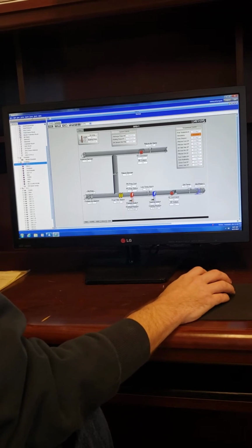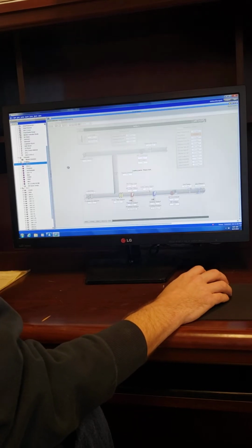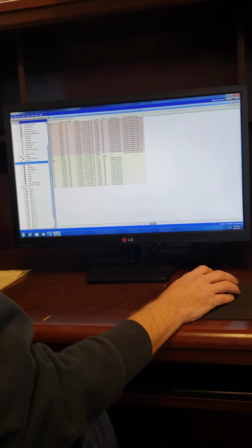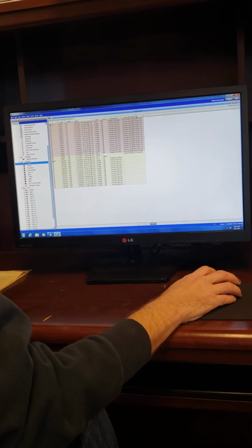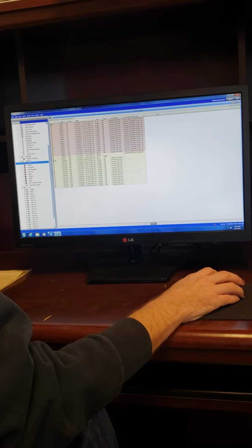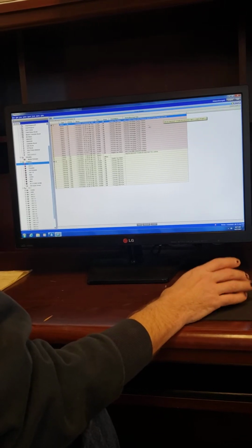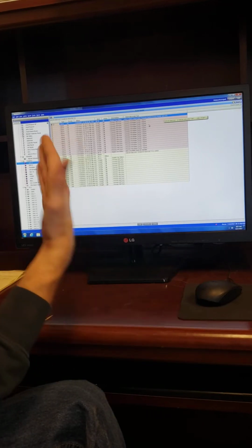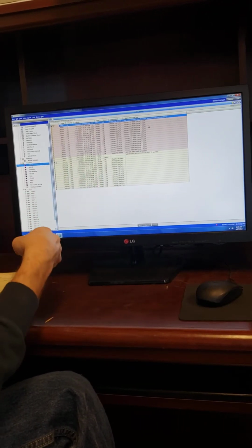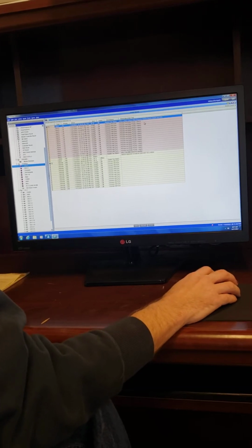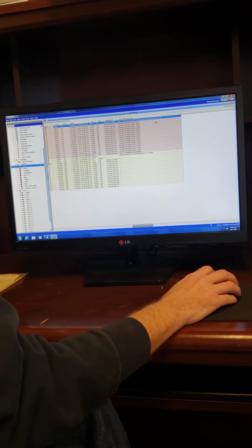So when your alarm comes up, see if it'll show me. Because I saw the alarm trigger, it actually tells you to check the high pressure switch or the freeze switch and the VFD. That high pressure switch was the black button that we reset on air handler 2. I'm not quite sure which one has tripped for number 1 just now, but we do want to go out and reset that also.